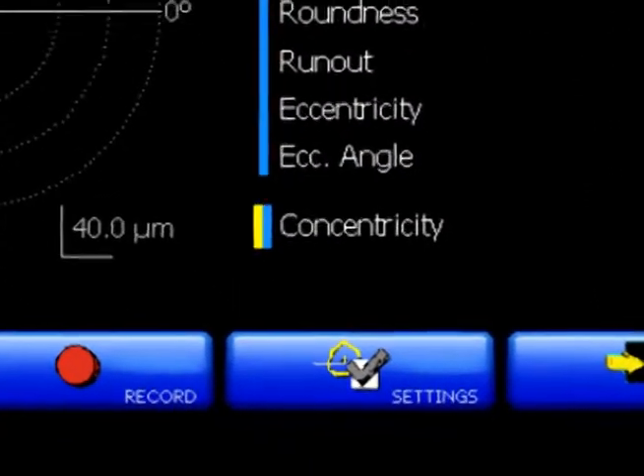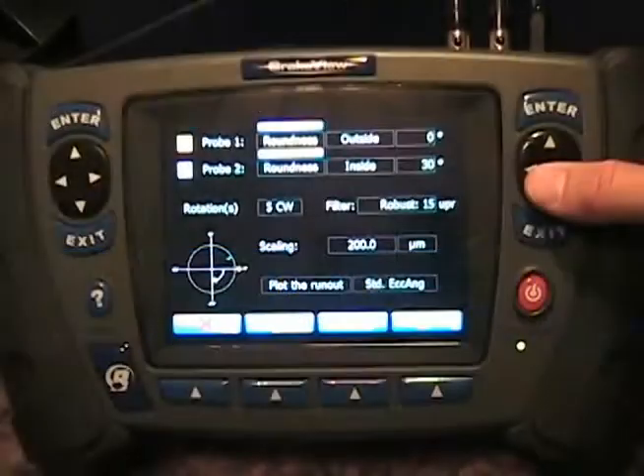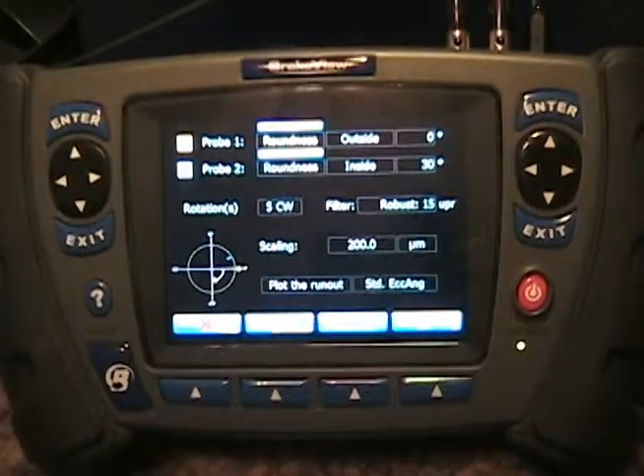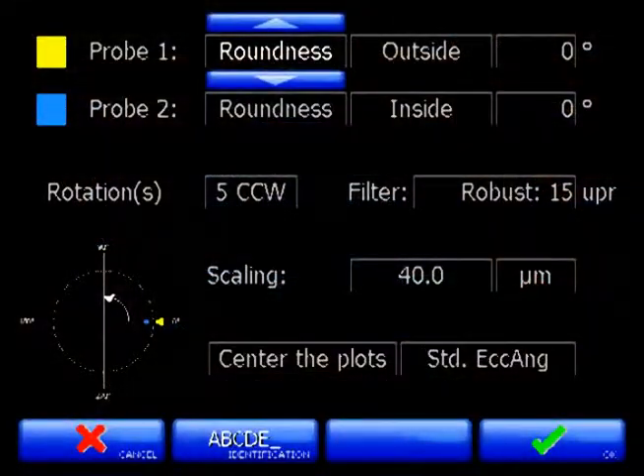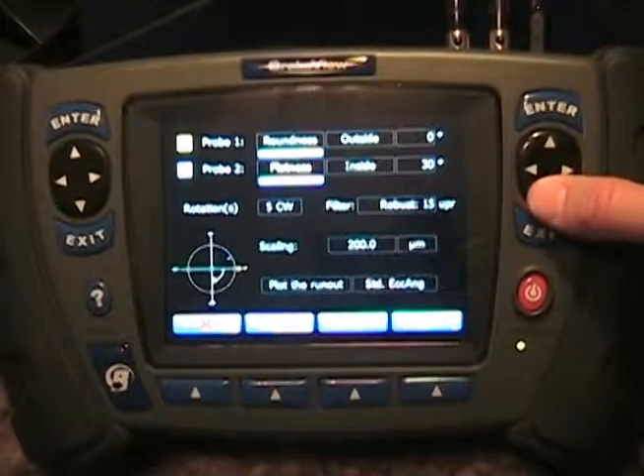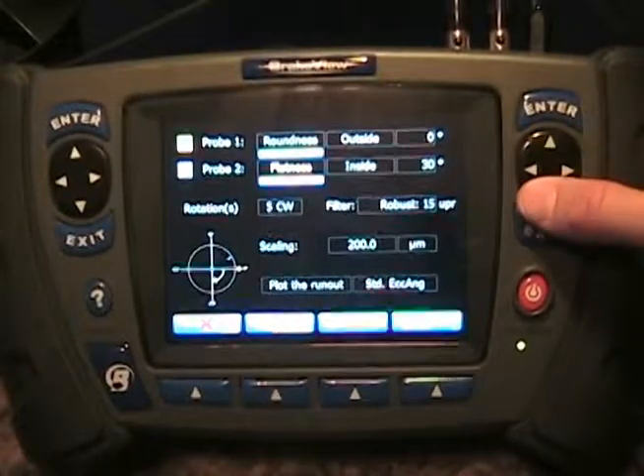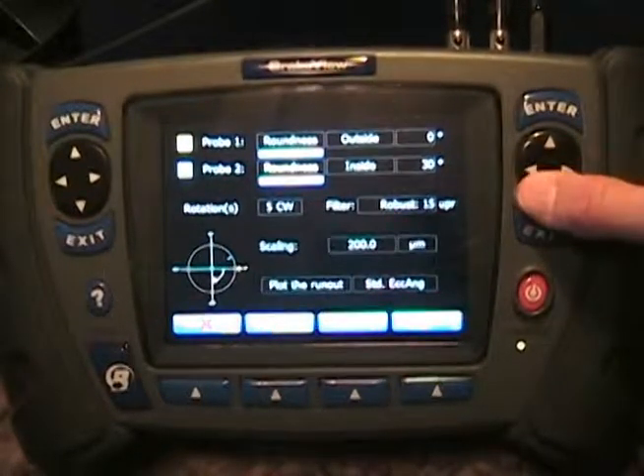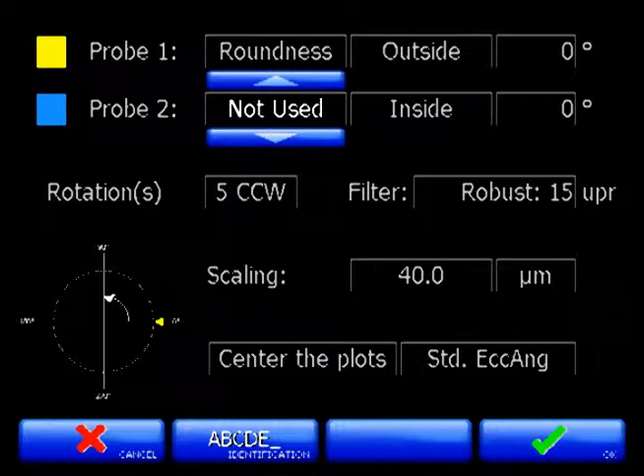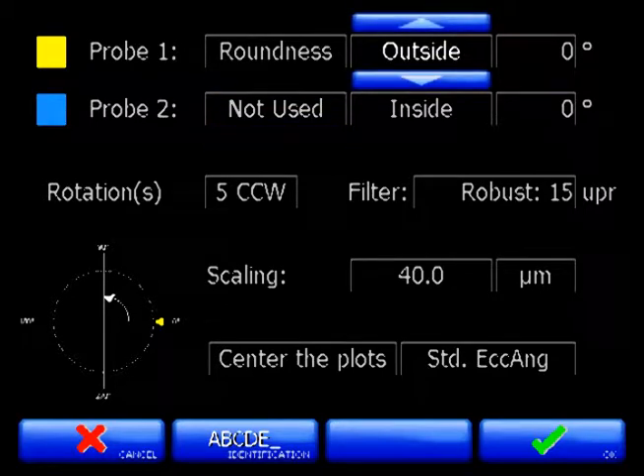Before making our roundness measurement, we need to tell the BrakeView system the kind of measurement we want to make. So the roundness settings screen gives us the ability to configure these kinds of measurements. You'll notice the roundness settings screen has positions for 2 different probes, our yellow probe and our blue probe at the top. And those probes can be set for roundness, flatness, or they can be turned off or put in a not used mode. In this case, we'll choose roundness with the yellow probe only. A roundness measurement can occur on an inside or an outside of a part. We'll choose outside in this case.